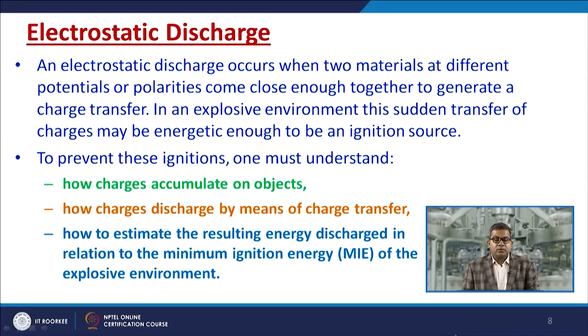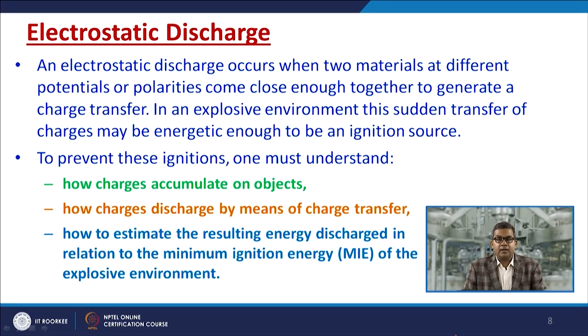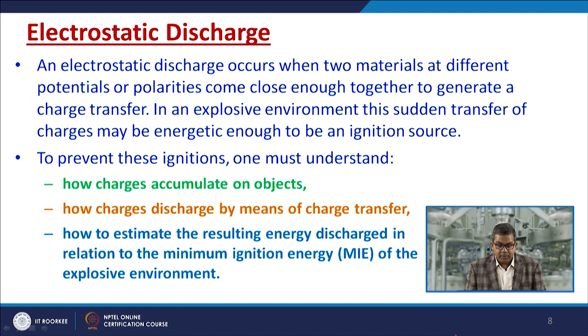An electrostatic discharge usually occurs when two materials at different potentials or polarities come close enough together to generate a charge transfer. In an explosive environment, this sudden transfer of charge may be energetic enough to be a source of ignition. To prevent this, one must understand how charge accumulates on an object, how charges are discharged by charge transfer, and how to estimate the resulting energy discharge relative to the minimum ignition energy of the explosive environment.